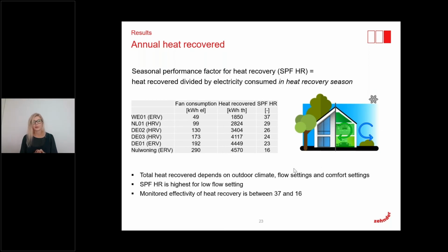The seasonal performance factor for heat recovery is low when the flow settings are high, and higher when the flow settings are lower. Therefore, we have more heat recovery area per cubic meter per hour, and the electricity for fan consumption is lower, so the value will be higher. But overall, when we think about the annual costs and savings and energy efficiency, then with this heat recovered ventilation, we are definitely adding value to the overall system.